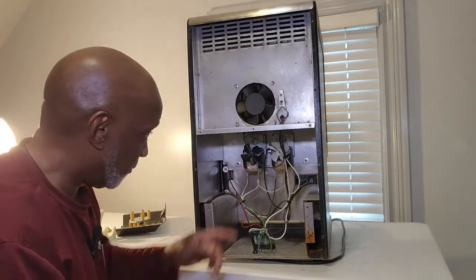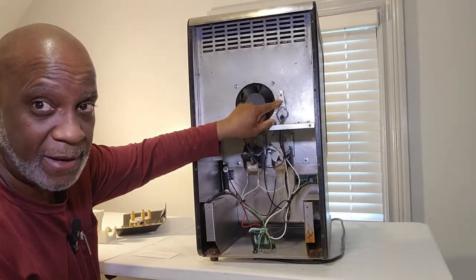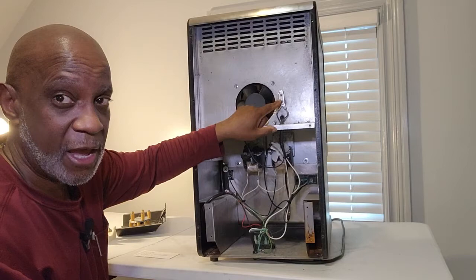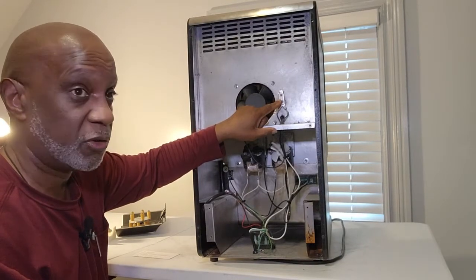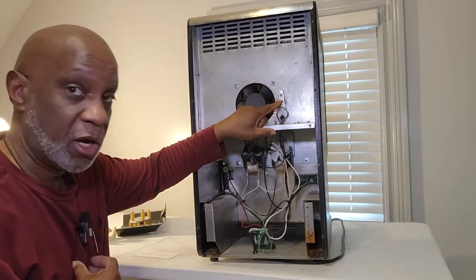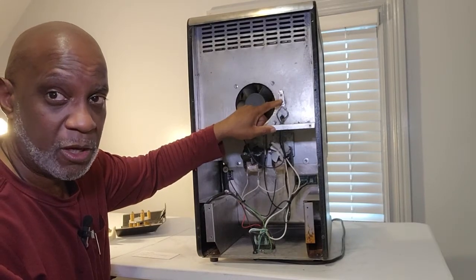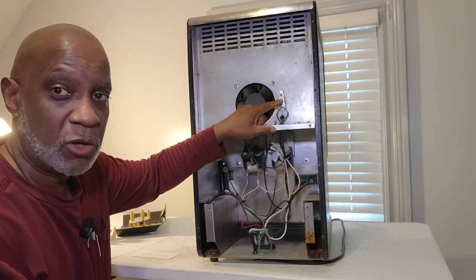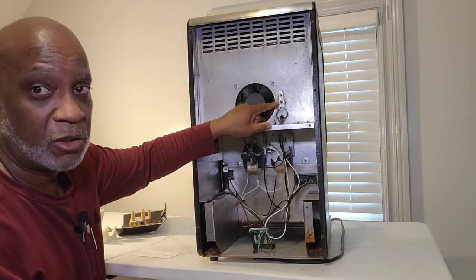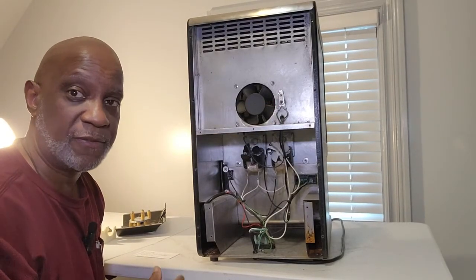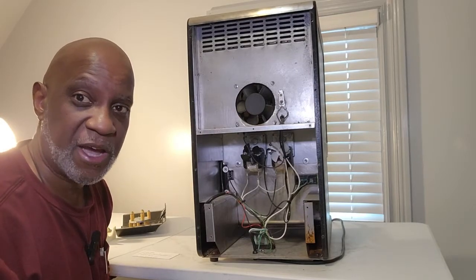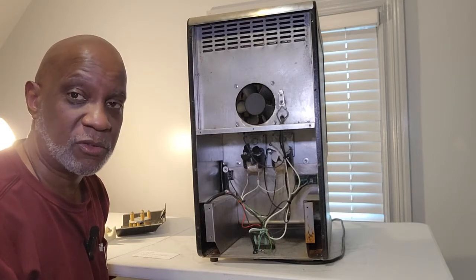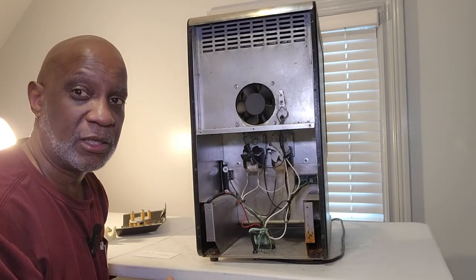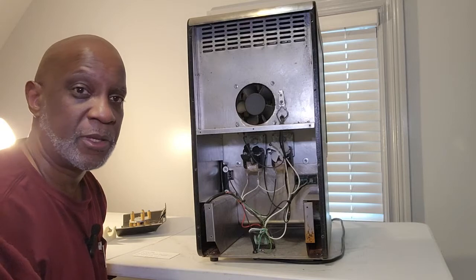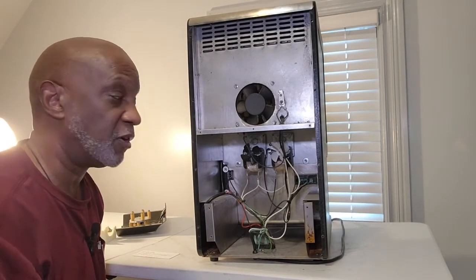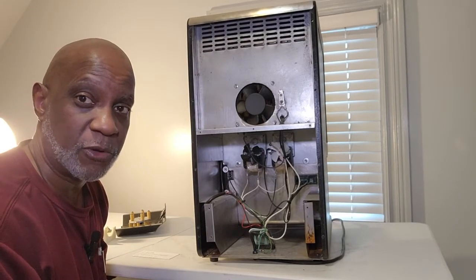So we have our high limit thermostat here. It's rated at 165 degrees. Just remember that if you're ever looking for a similar thermostat, make sure it's rated for 165 degrees, because on these you set the set point at 145 or 150. I usually go with 150, but some other technicians go with 145. It's fine either way, as long as it's keeping it above 140.